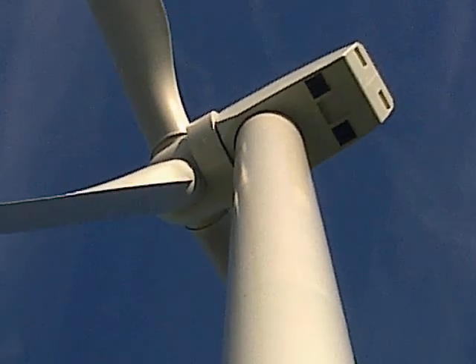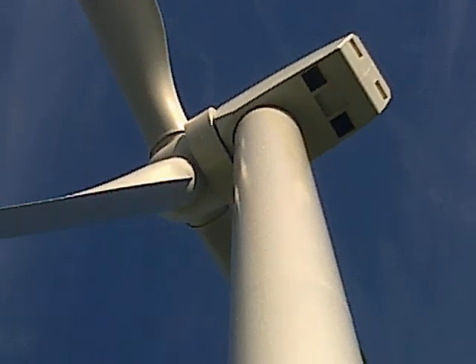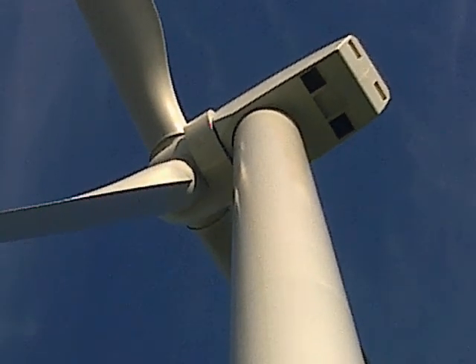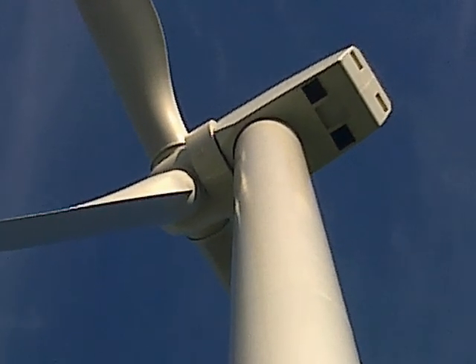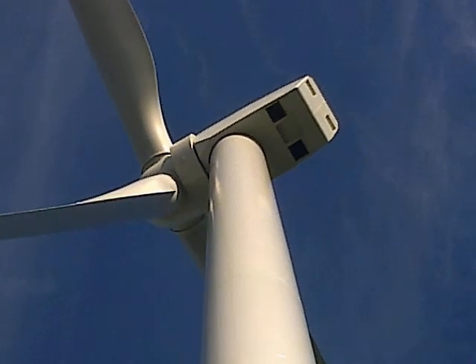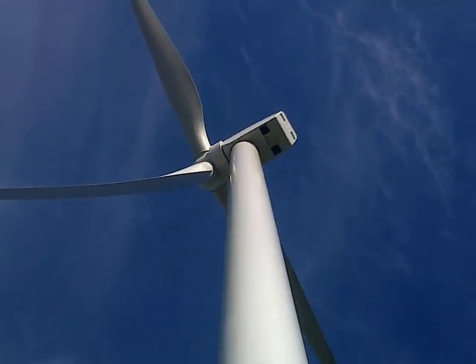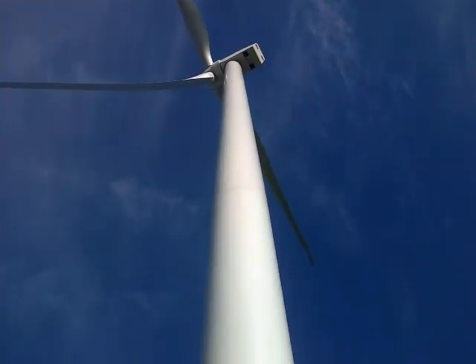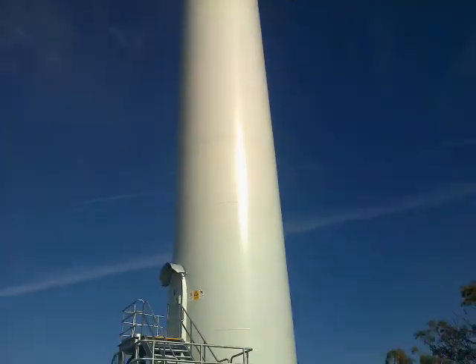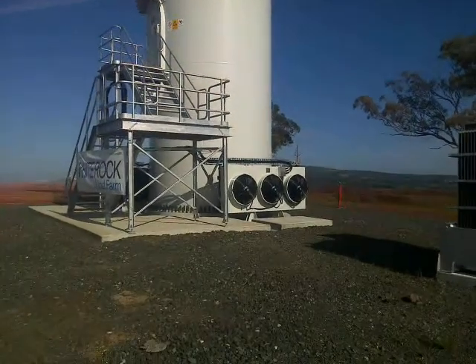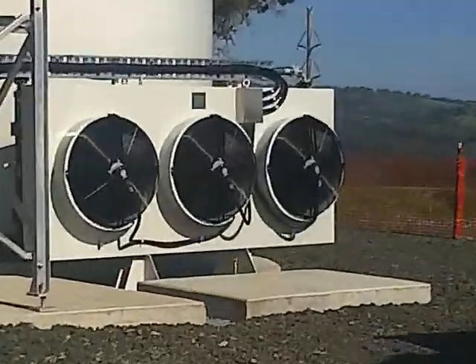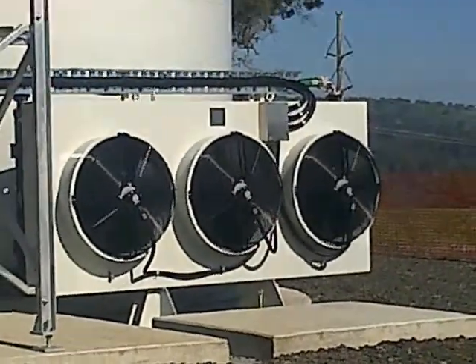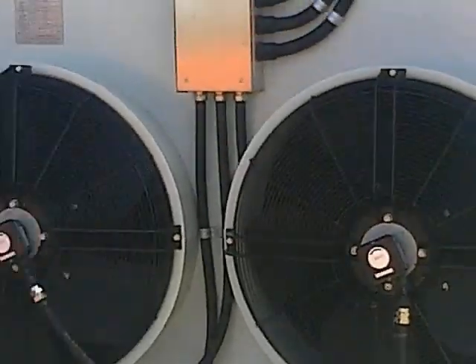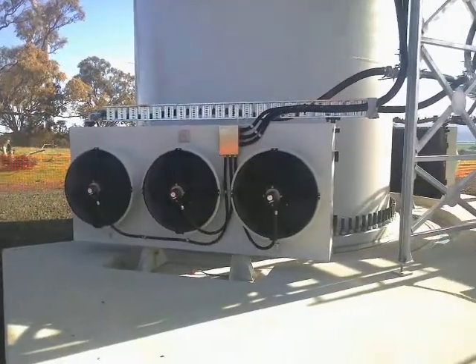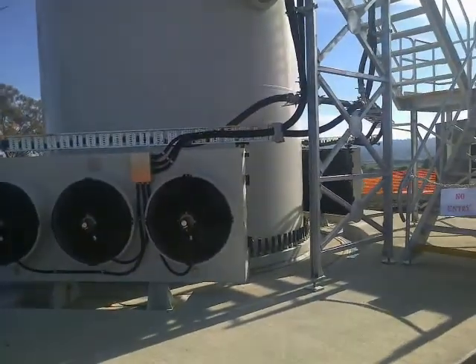I may be wrong about this, but my understanding is that there are giant neodymium permanent magnets on the rotor, with the coils all in the turbine head. It produces direct current electricity, runs that down the steel tower, and down at ground level they have great big solid-state inverters on two sides of the tower to take advantage of the prevailing wind for cooling.